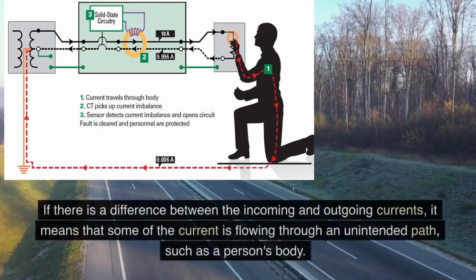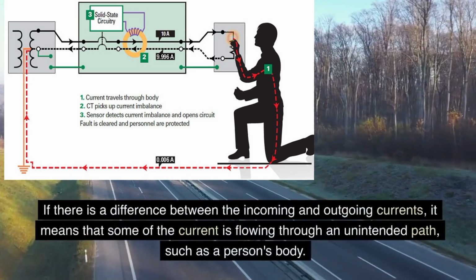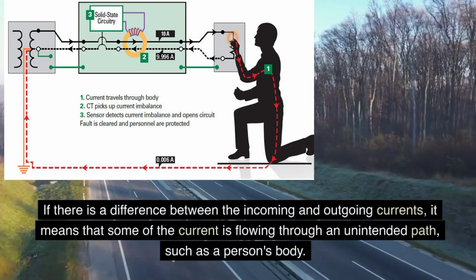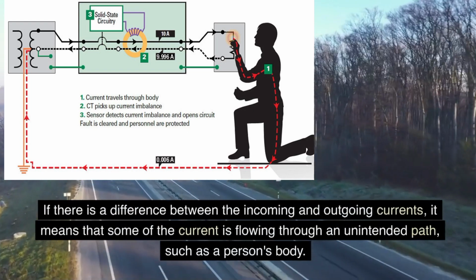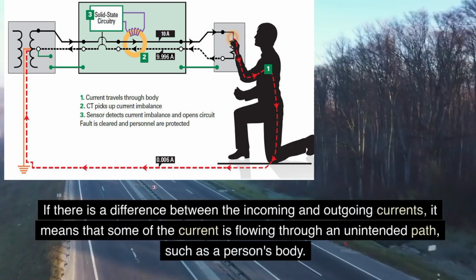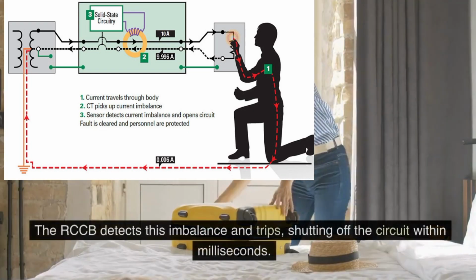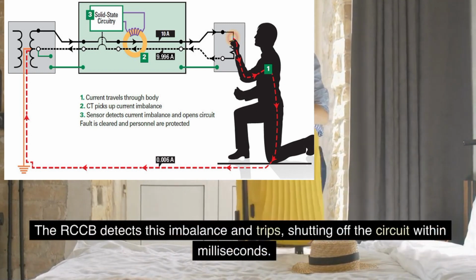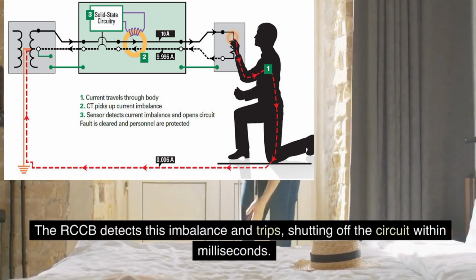If there is a difference between the incoming and outgoing currents, it means that some of the current is flowing through an unintended path, such as a person's body. The RCCB detects this imbalance and trips, shutting off the circuit within milliseconds.